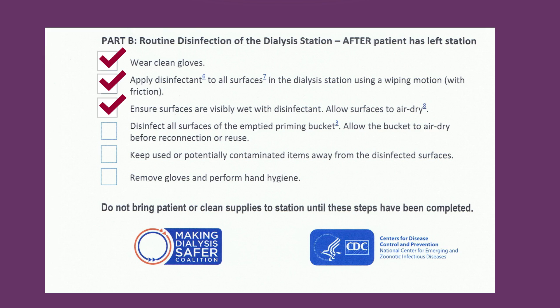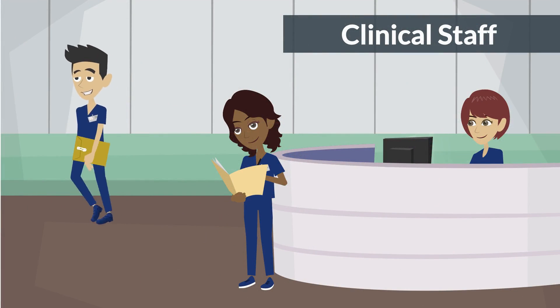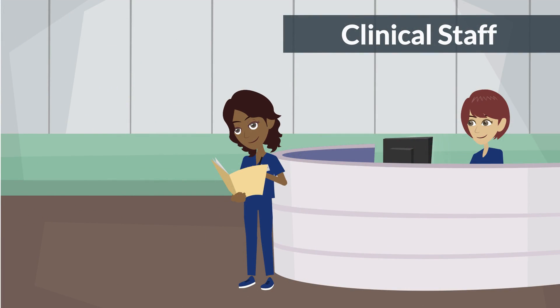Ensure surfaces are visibly wet with disinfectant. Allow surfaces to air dry. Disinfect all surfaces of the emptied priming bucket. Allow the bucket to air dry before reconnection or reuse. Keep used or potentially contaminated items away from the disinfected surfaces. Remove gloves and perform hand hygiene. Do not bring patient or clean supplies to the station until these steps have been completed. This completes the environmental cleaning process between patient treatments, which is usually the responsibility of the clinical staff.